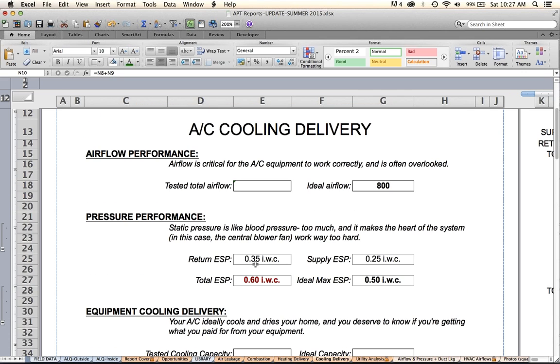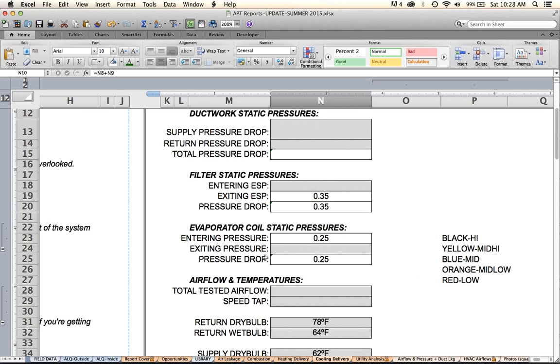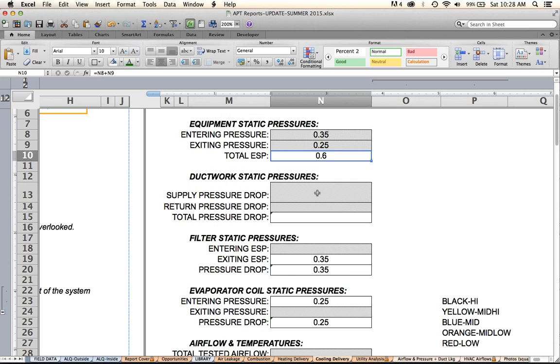You can see right here that I have explained for my homeowner the pressure performance. Static pressure is like blood pressure. Too much, and it makes the heart of the system, in this case the central blower fan, work way too hard. So I've got my return external static pressure, my supply external static pressure. Both of these are in inches of water column, which is how you always measure HVAC pressures. The total is in red because it happens to be over this. So that's what we want to be able to pinpoint. So here we can see that the return is having a much harder time than the supply. This return is giving more pressure, more pushback, essentially, to the fan. So now let's figure out what exactly the problem is.